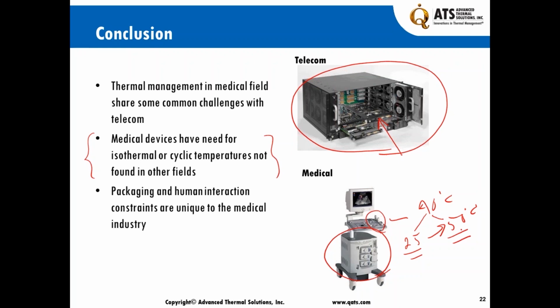And as a result, the thermal challenge, taking the heat away from the surfaces and being able to discharge it in the equipment, or in the air in the back of the unit, or put it into the cooling system of the building, all become a part of the design process that we have to go through. Hence, we need to know the deployment site for the equipment that's going to be released and designed. That is really, really important, as we've talked about in other webinars.